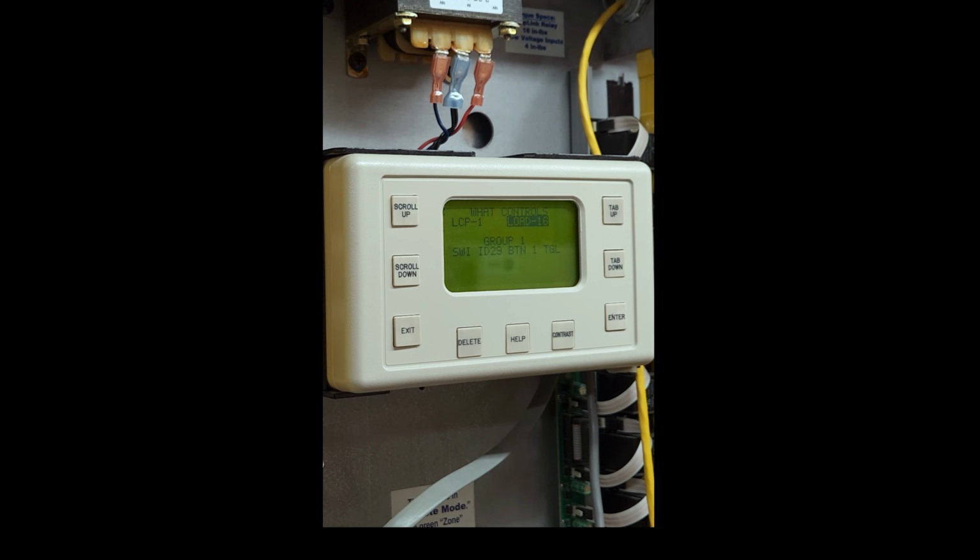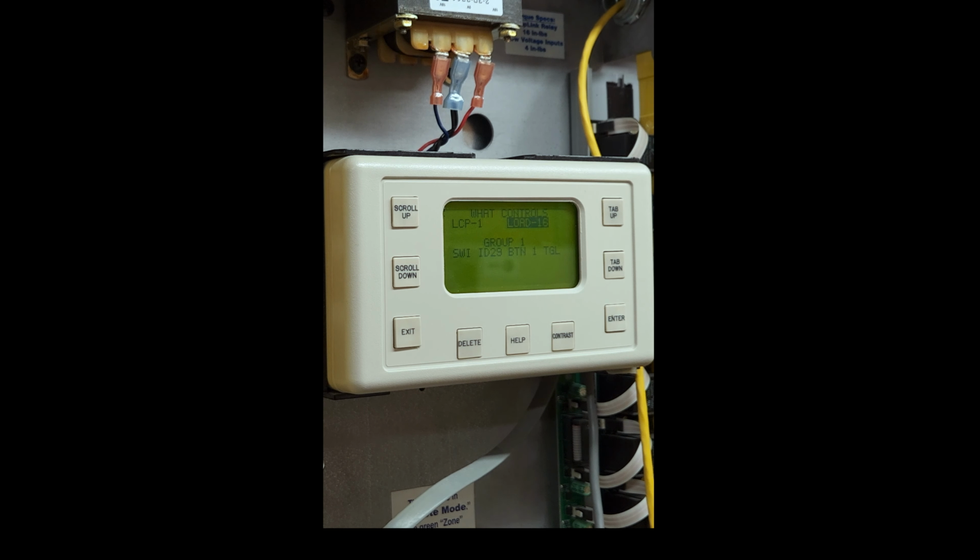But I can promise you, if you find that switch you're referring to, and you take it out of the wall and bring a patch cable and hook it up directly to this panel, the panel can see it, and the switch will be working. But wherever the switch is, because they are daisy chained together, the panel does not see them. Okay. You have a disconnect somewhere.